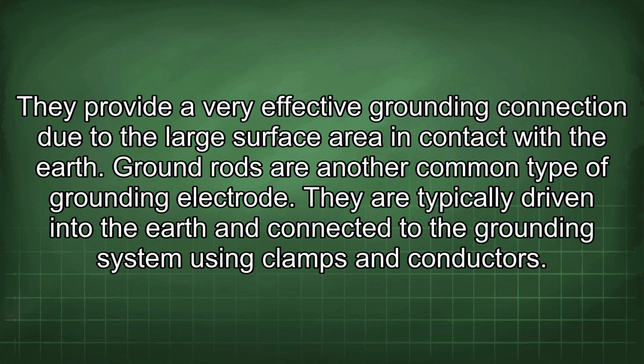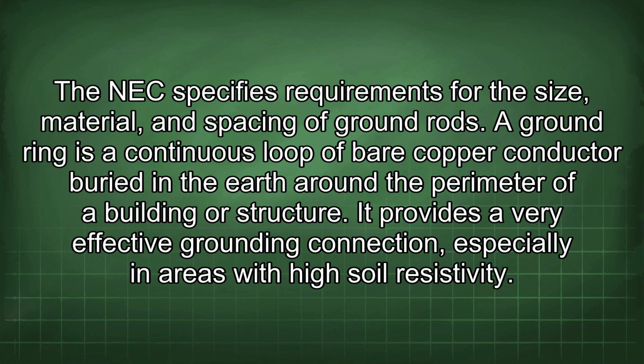Ground rods are another common type of grounding electrode. They are typically driven into the earth and connected to the grounding system using clamps and conductors. The NEC specifies requirements for the size, material, and spacing of ground rods. A ground ring is a continuous loop of bare copper conductor buried in the earth around the perimeter of a building or structure. It provides a very effective grounding connection, especially in areas with high soil resistivity.